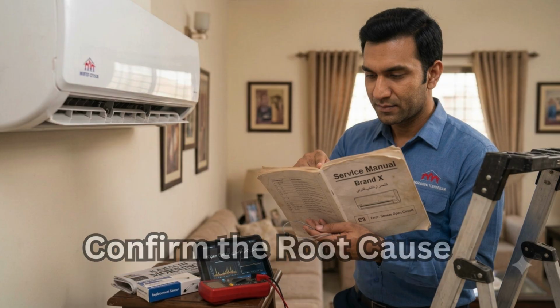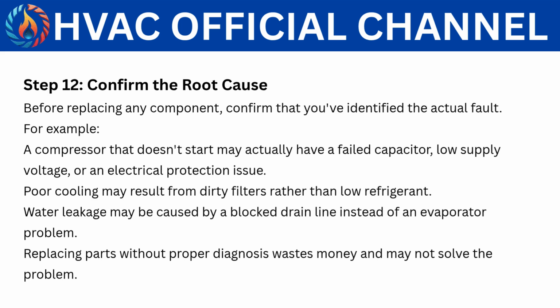Step 12. Confirm the root cause. Before replacing any component, confirm that you've identified the actual fault. For example, a compressor that doesn't start may actually have a failed capacitor, low supply voltage, or an electrical protection issue. Poor cooling may result from dirty filters rather than low refrigerant. Water leakage may be caused by a blocked drain line instead of an evaporator problem. Replacing parts without proper diagnosis wastes money and may not solve the problem.